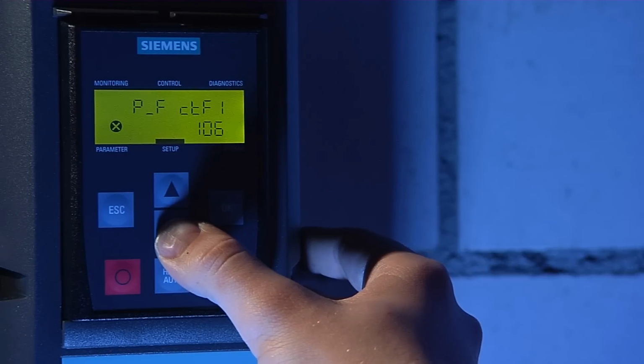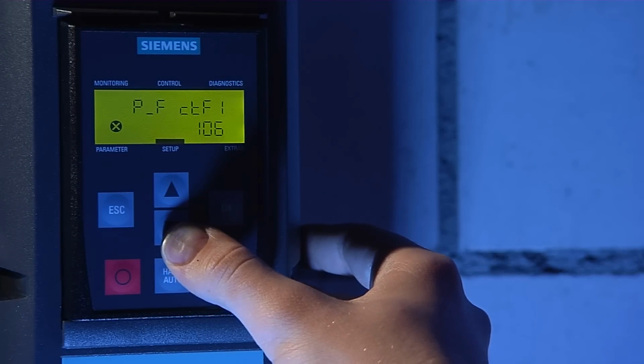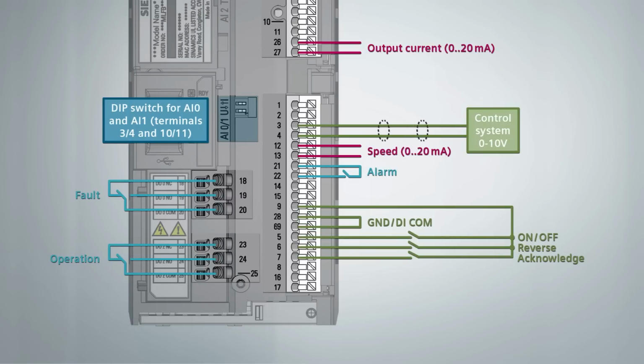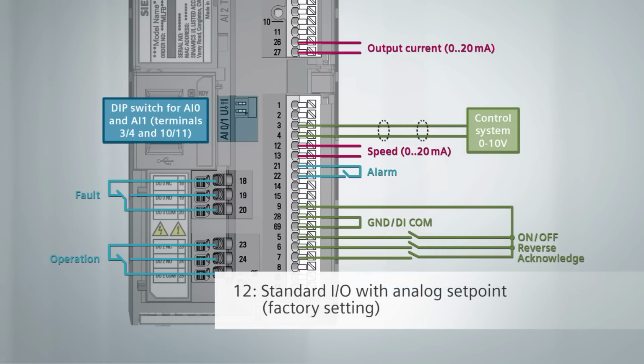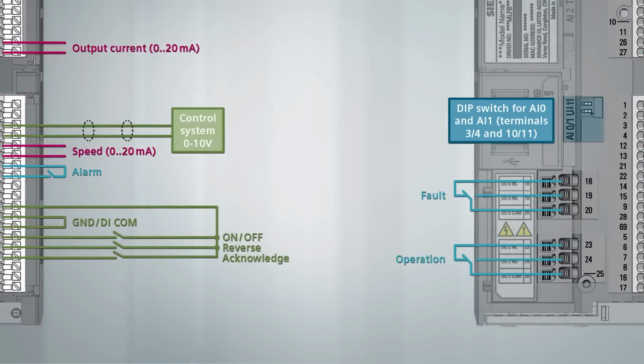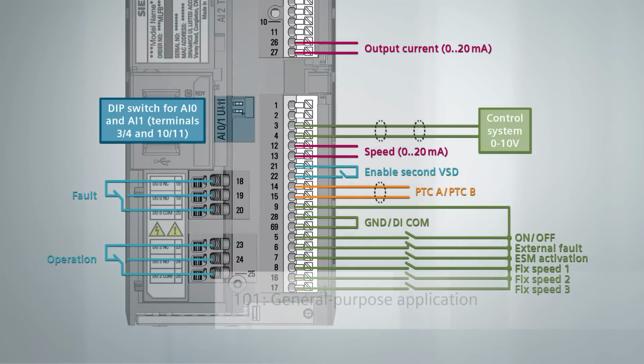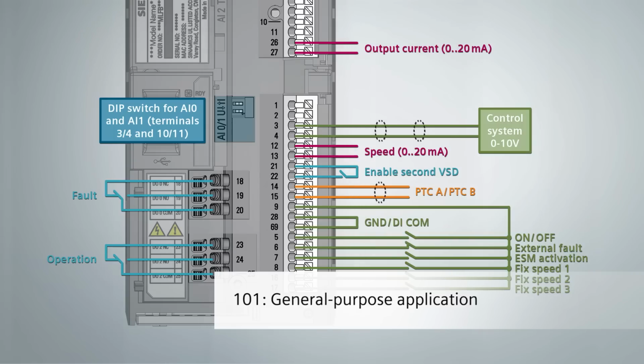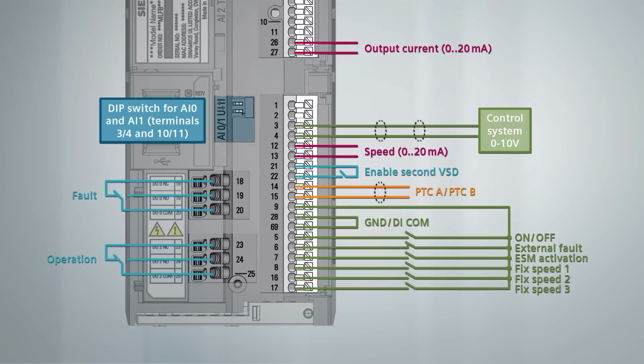The HVAC-relevant macros implemented in the G120P are the following. Macro 12, Standard I/O with analog setpoint, factory setting: 0 to 10 volt analog set point and digital input on command. Macro 101, General purpose application, covers most of the basic applications: 0 to 10 volt set point, fixed speed override and essential service mode ESM. Please note, ensure the external fault input on digital input 1 is connected and energized to prevent this from disrupting the commissioning process.